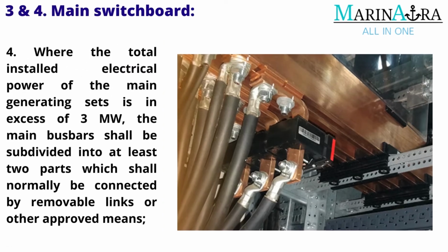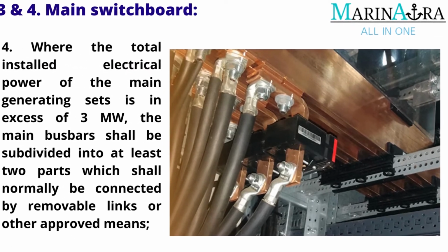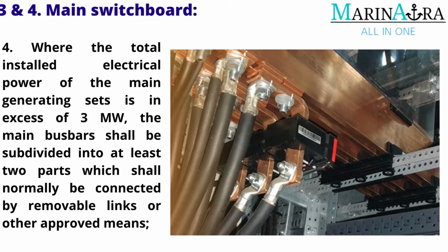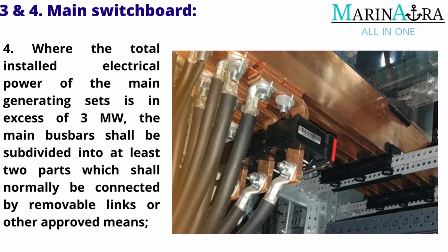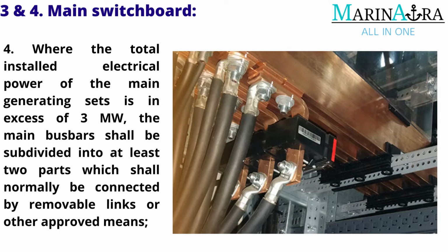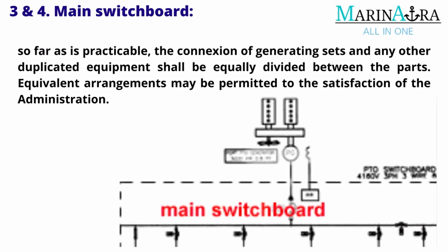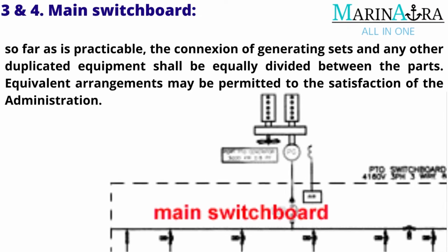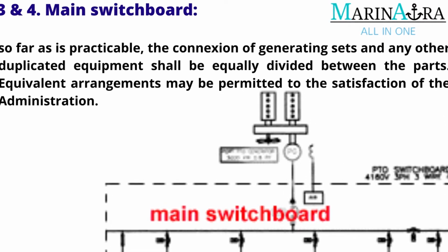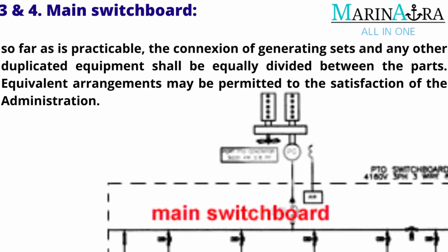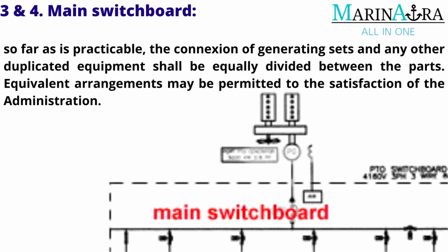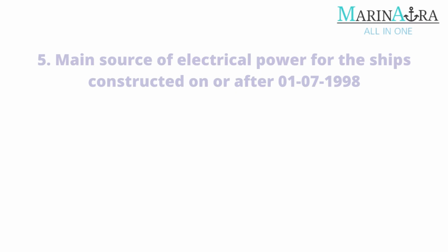Where the total installed electrical power of the main generating sets is in excess of 3 megawatts, the main busbars shall be subdivided into at least 2 parts which shall normally be connected by removable links or other approved means. So far as is practicable, the connection of generating sets and any other duplicated equipment shall be equally divided between the parts. Equivalent arrangements may be permitted to the satisfaction of the administration.